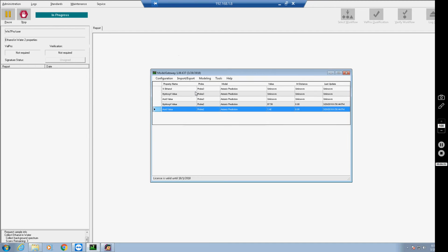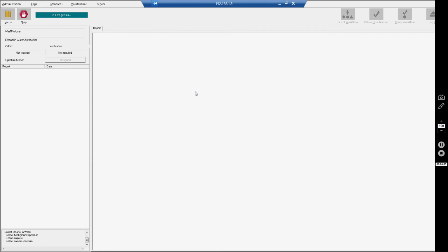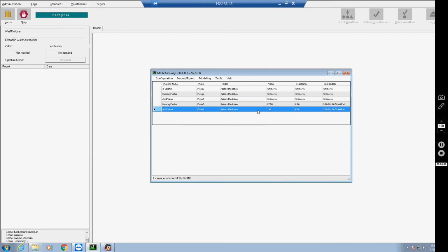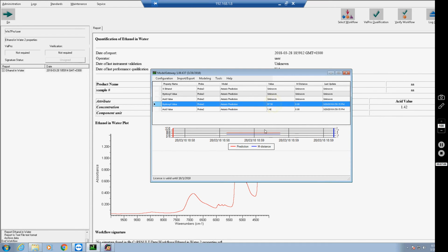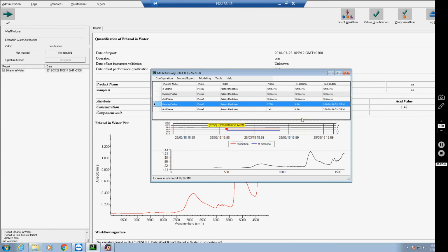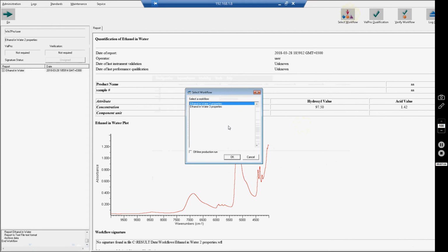We need at least 2 in order to show a graph. So I will just run it again. And you can see the timestamp changing here at the moment that we load the new data, from 44 seconds to 15 now. If I click on it, we have a graph with the first 2 points. Clicking on each one of them will show the spectrum. I will do the same for the second channel.